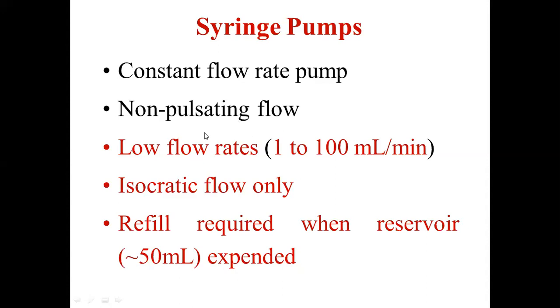They don't create any pulses, therefore they create non-pulsating flows, but they create very low flow rates, from 1 to 100 ml per minute. Whenever a lesser flow rate is required, we are going to use these syringe pumps. Whenever a high flow rate is required, we are going to use reciprocating pumps. And these are applicable only for isocratic flow, because we cannot connect the terminal of this pump to multiple solvent reservoirs. Only a single solvent reservoir can be connected to this pump, therefore isocratic flow can be created. And of course the refill is required, because this is a syringe-like object. Refill is required for the mobile phase in order to introduce it into the chromatography column while creating the pressure. So each and every refill will be occupying up to 50 milliliters of the mobile phase.